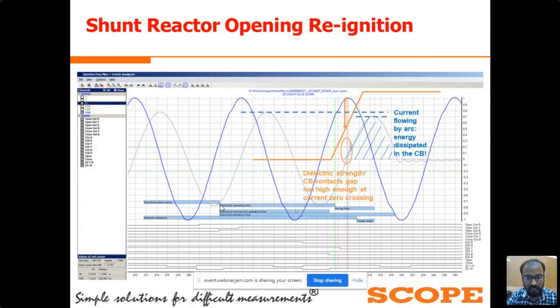From here, this is a predicted operating time, that is, the breaker opening time. So the CSD executed the command here without taking any reference of system voltage, because the CSD is out of service. So the CSD executed the command near to this point. Here you can see this is a graph generated, that is a predicted operating time.